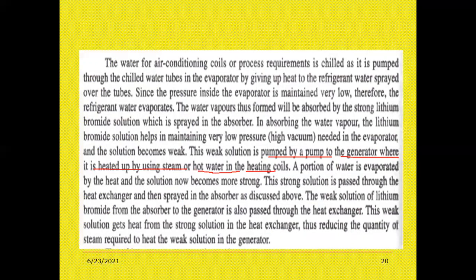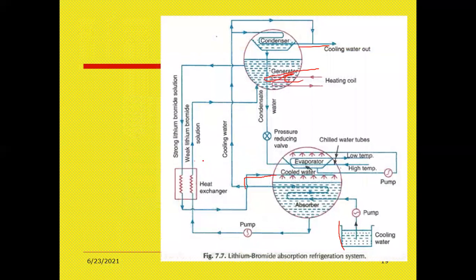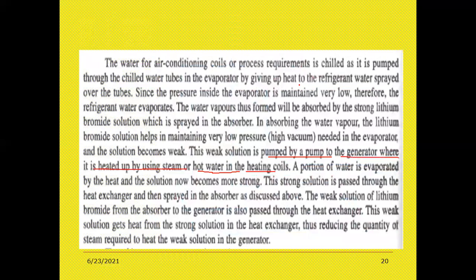What is it they are saying? The weak solution is pumped by the pump to the generator. So this pump will pump the weak lithium bromide solution to the heat exchanger, and then to which one? To the generator. Yes, it is pumped to the generator.